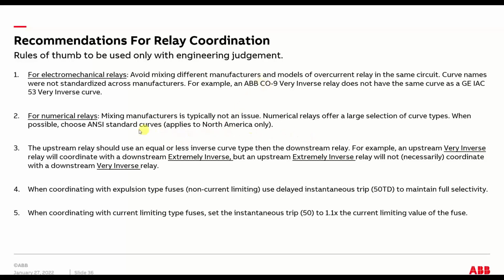And I would choose ANSI standard curves for applications in North America. There's an IEC version of those curves too, which is different. So if you're outside the U.S., Europe, I think Asia too, would tend towards using IEC type curves. Yeah, this is kind of important. Usually you try to keep the type of curve, whether it's extremely inverse or very inverse, you try to keep it the same on all your devices.